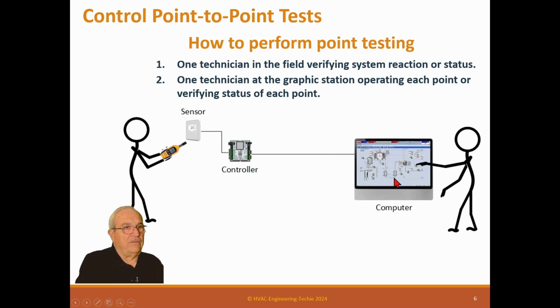And another thing for these systems, we normally have a control contractor there to help us with the system, but we have our people or an operator help us do this, because you're going to say, all right, I show 75 degrees at the wall sensor. And the operator will tell you, well, I show 79 degrees on that wall sensor. So we know we've got a difference of 4 degrees, and that's a little much. We'll talk about what we do with that later on.